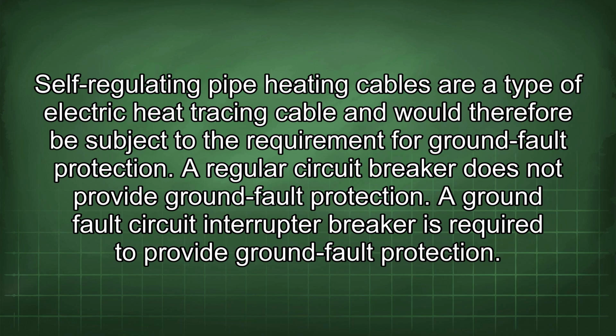Self-regulating pipe heating cables are a type of electric heat tracing cable and would therefore be subject to the requirement for ground fault protection. A regular circuit breaker does not provide ground fault protection. A ground fault circuit interrupter breaker is required to provide ground fault protection.